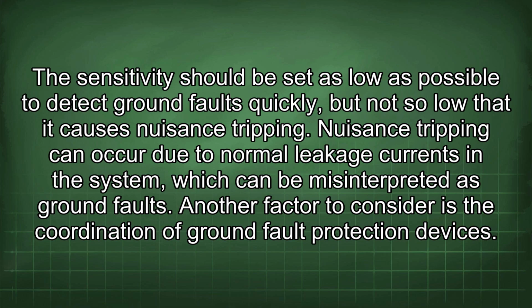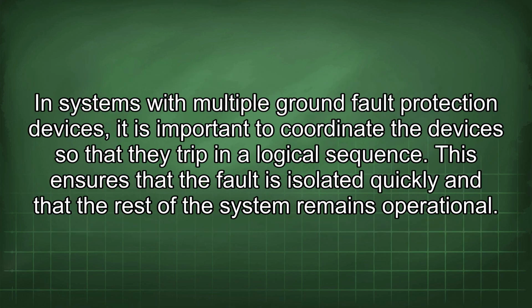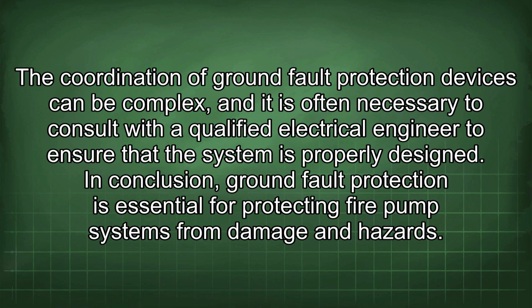Another factor to consider is the coordination of ground fault protection devices. In systems with multiple ground fault protection devices, it is important to coordinate the devices so that they trip in a logical sequence. This ensures that the fault is isolated quickly and that the rest of the system remains operational. The coordination of ground fault protection devices can be complex, and it is often necessary to consult with a qualified electrical engineer to ensure that the system is properly designed.